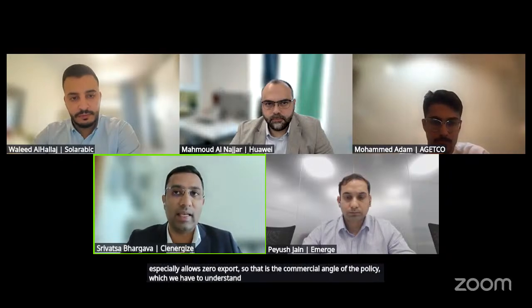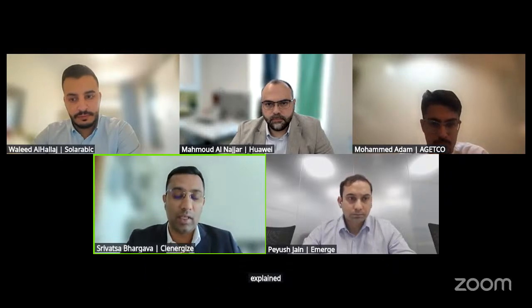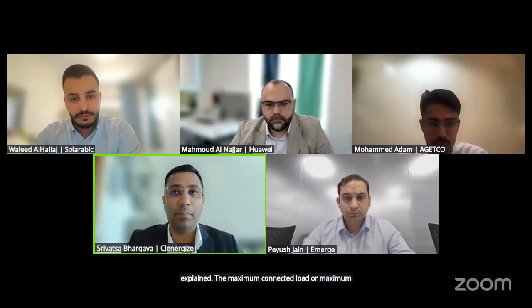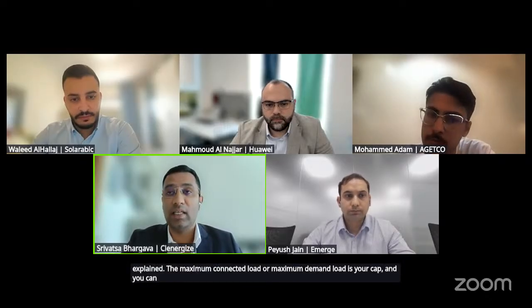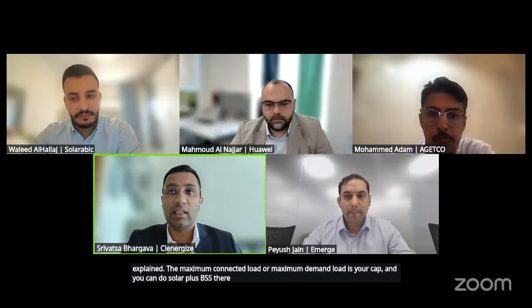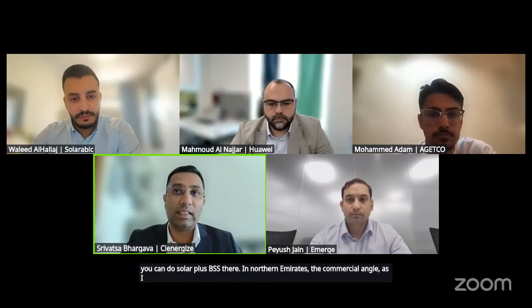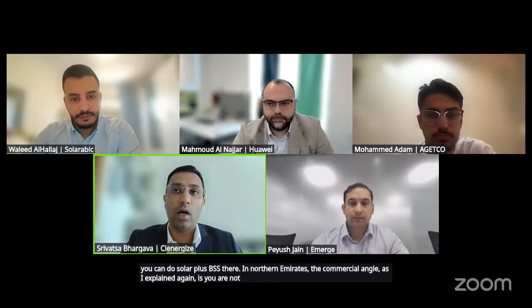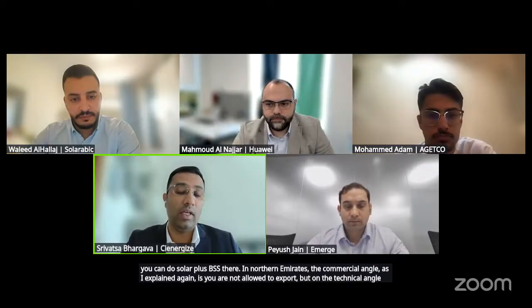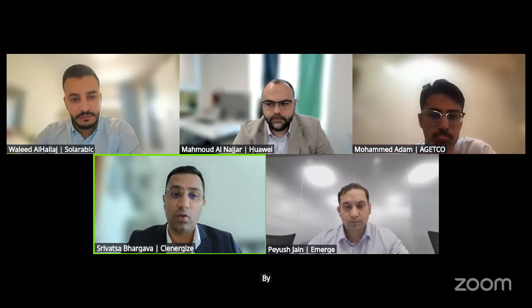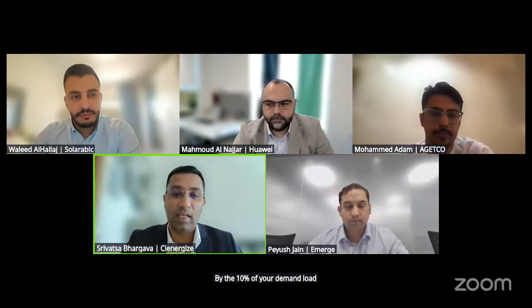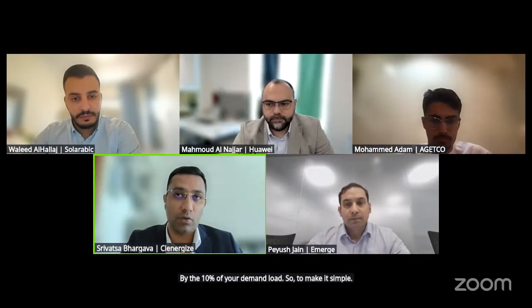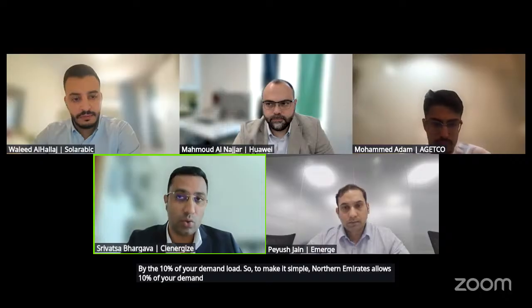On the technical angle, as I explained, the maximum connected load or maximum demand load is your cap, and you can do solar plus BSS there. In Northern Emirates, the commercial angle, as I explained again, is you are not allowed to export. But on the technical angle of it, you are only limited by the 10% of your demand load. So to make it simple, Northern Emirates allows 10% of your demand load. You can do solar plus BSS.